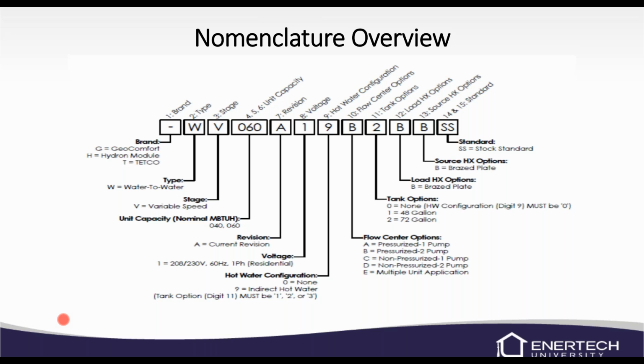The next will be the type of unit. This is a water-to-water unit, so it'll be designated with a W. The third digit is the staging. You guys are probably real used to seeing a T or an S for two-stage or single stage. Now we have a V for the variable speed. Then we have the unit capacity, again, either 040 or 060. The next is a revision. That's more if we were to change the brand of brace plate that we put in the unit, or we were to upgrade the compressor to the newer variable speed. We would change the revision because something major inside that system has been changed.